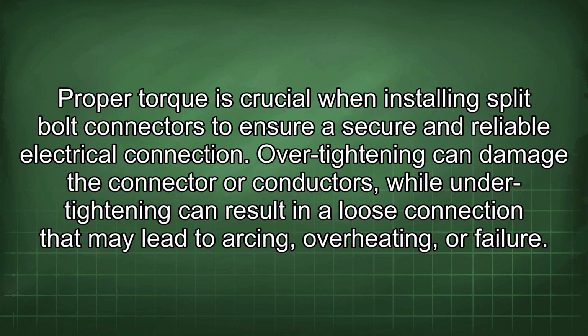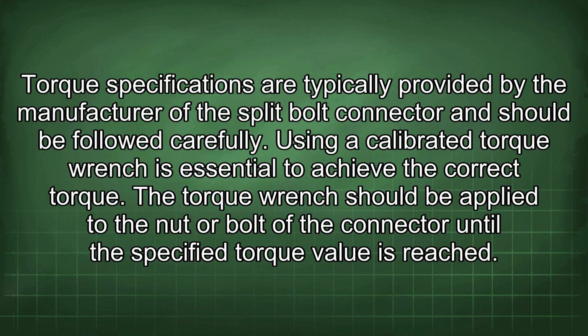Proper torque is crucial when installing split-bolt connectors to ensure a secure and reliable electrical connection. Over-tightening can damage the connector or conductors, while under-tightening can result in a loose connection that may lead to arcing, overheating, or failure. Torque specifications are typically provided by the manufacturer of the split-bolt connector and should be followed carefully. Using a calibrated torque wrench is essential to achieve the correct torque.